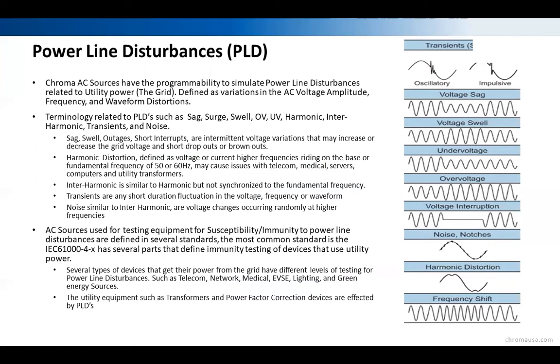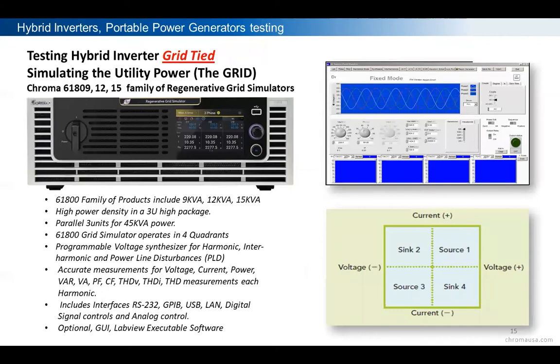You need to know how your hybrid inverter output, when it's putting power back on the grid, would respond to various transients or power line disturbances. We have that ability to generate all of the different kinds of power line disturbances that are defined in the IEC 61000-4 standards for susceptibility and immunity for power line disturbances. So by doing that, we've created this incredible software package.